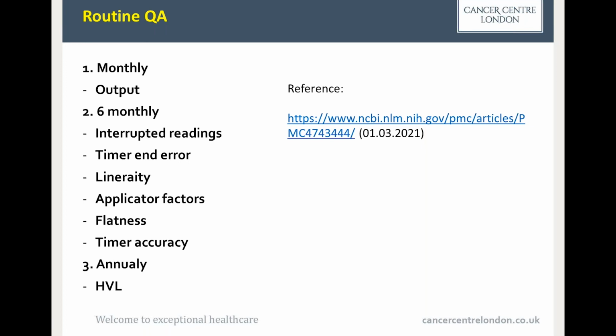We have also prepared baselines for routine QA, and we have started to regularly measure specific parameters which are in line with the valid code of practice. Monthly we check output really only for the reference applicator. Six-monthly we also check some safety aspects, applicators, factors, linearity. It means whether the system behaves linearly in terms of time and delivers the dose.